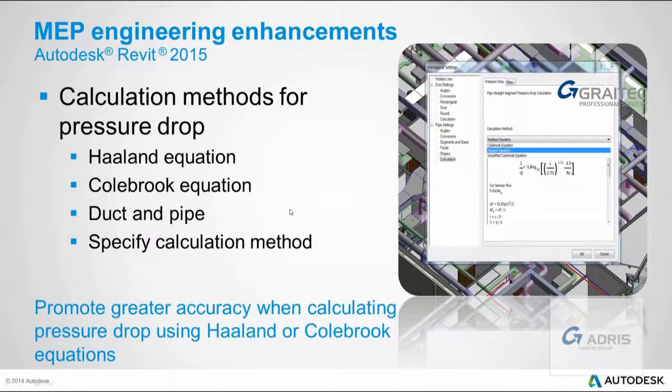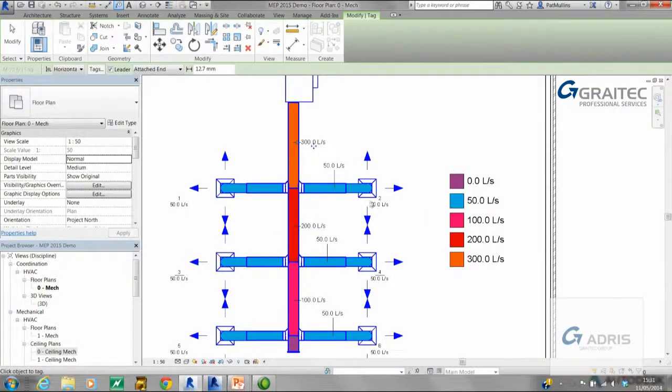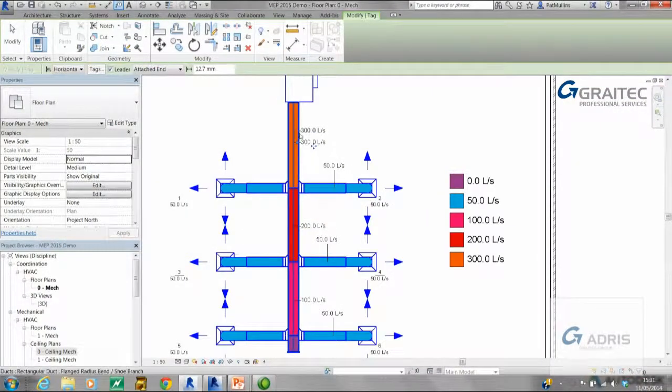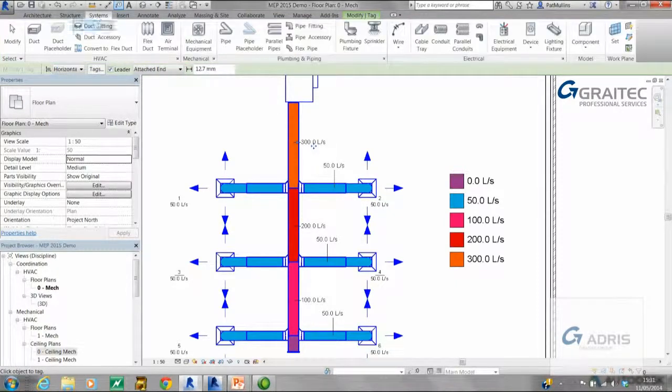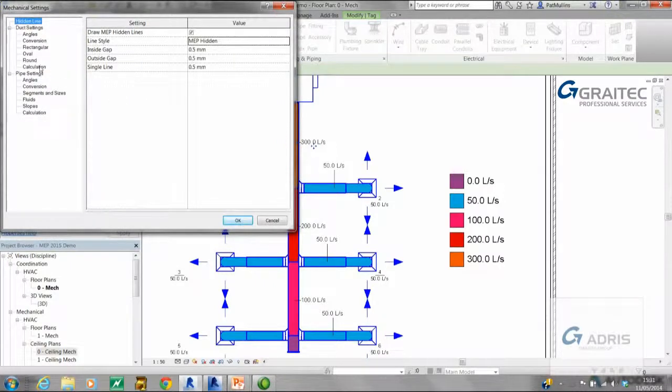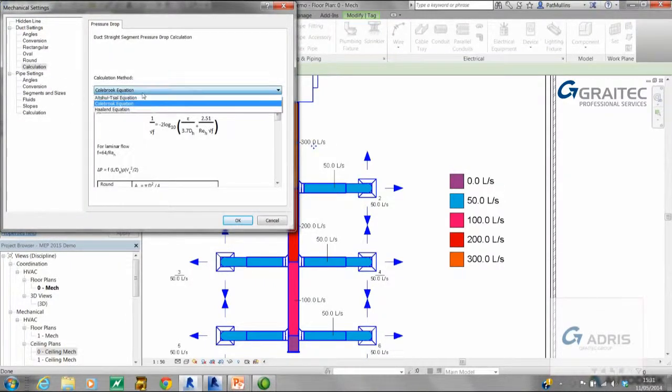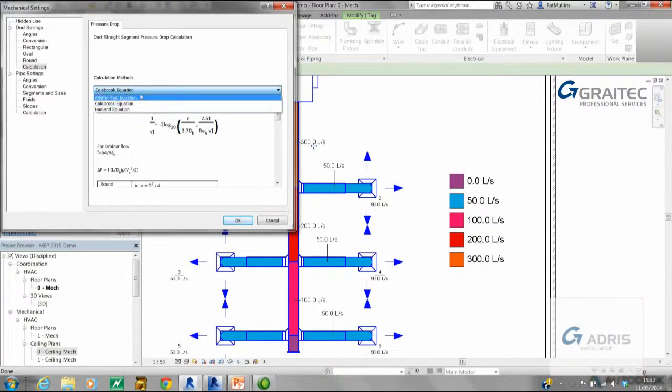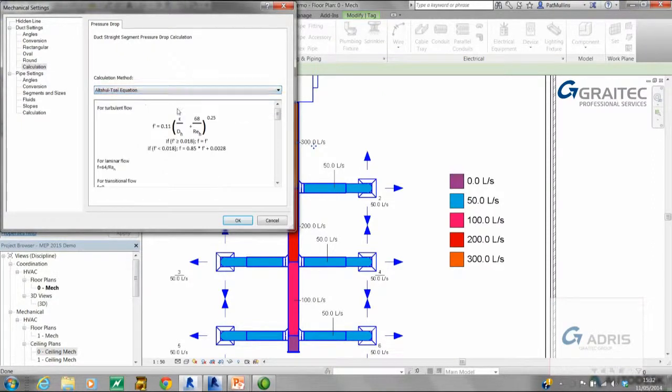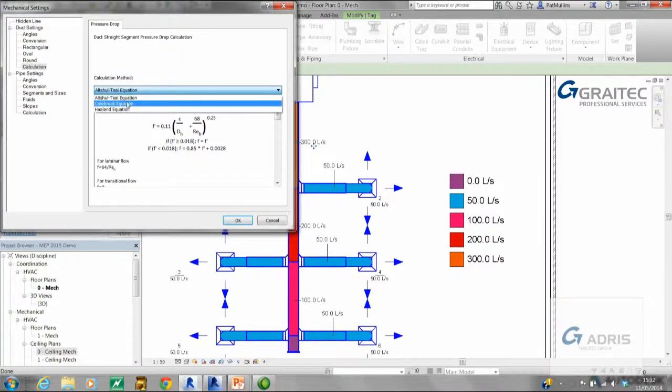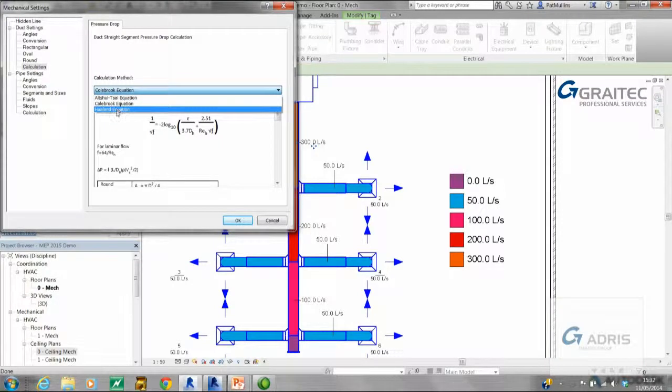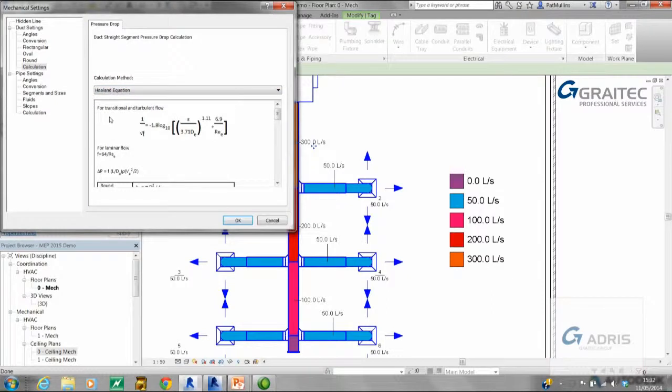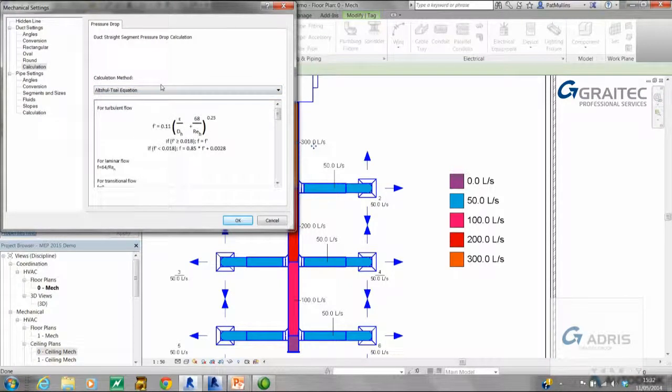Second improvement: calculation methods for pressure drop. Let's delve into 2015 and take a look at mechanical settings for ductwork. You'll now see that we have some additional equations or calculation methods specified. The default was turbulent flow. There have been two additions: Colebrook equation, which is transitional and turbulent, and also the Haaland, which is also transitional and turbulent. So two new calculation methods have been added in 2015.